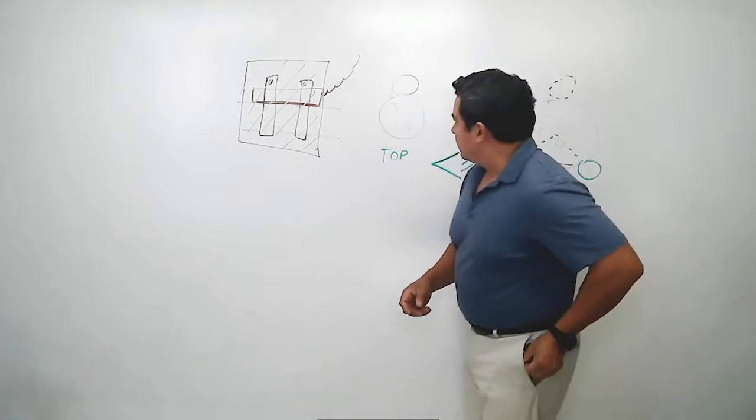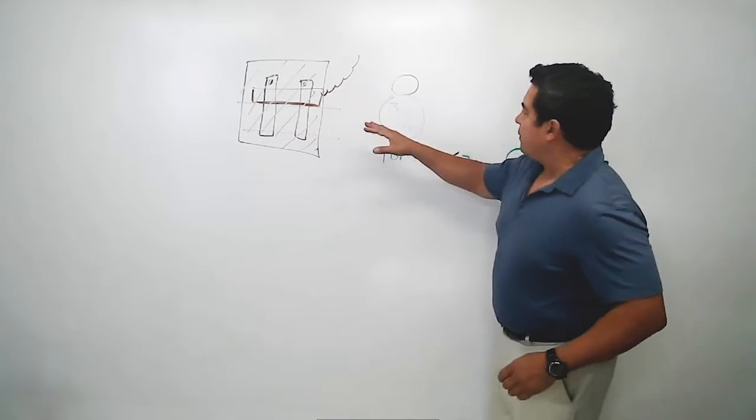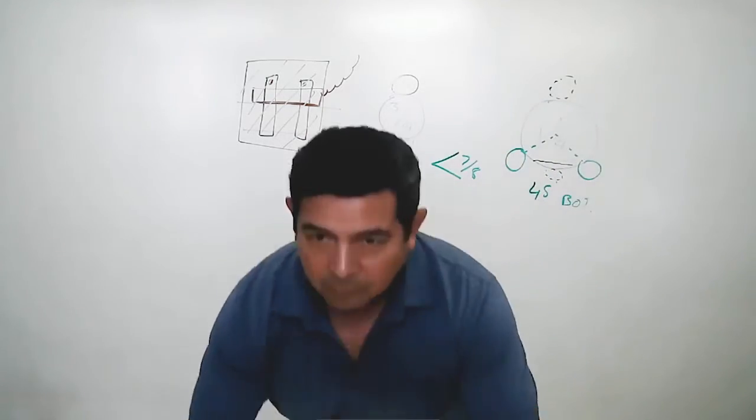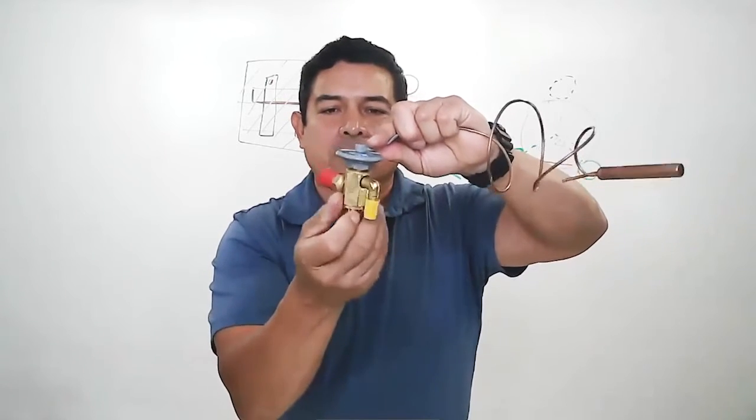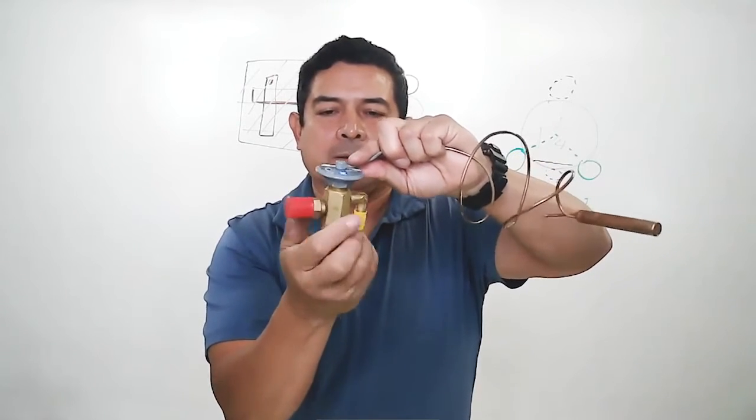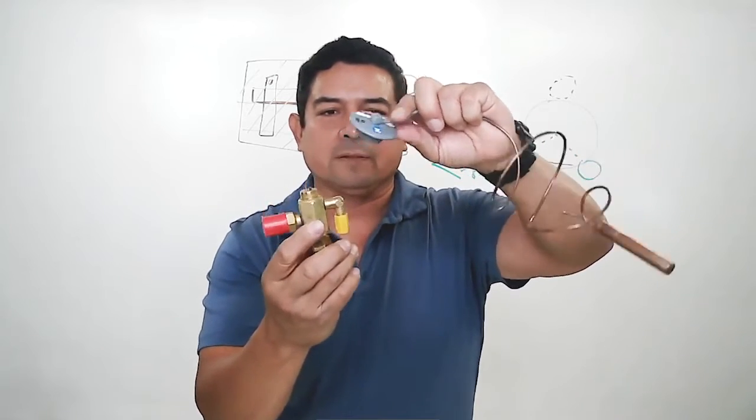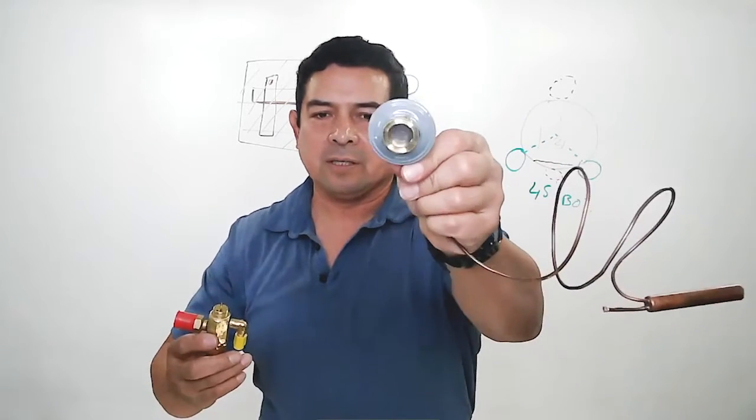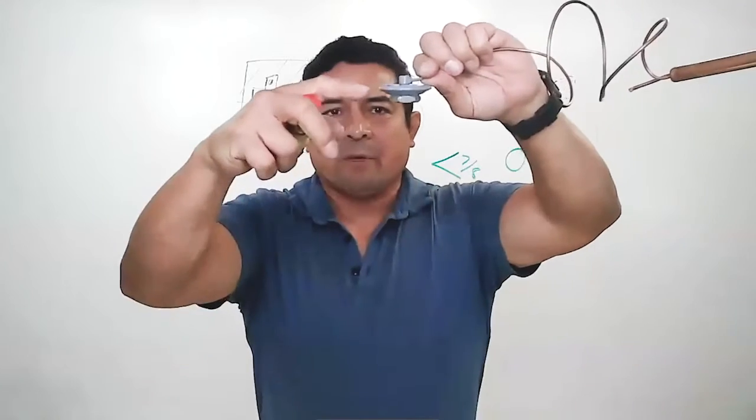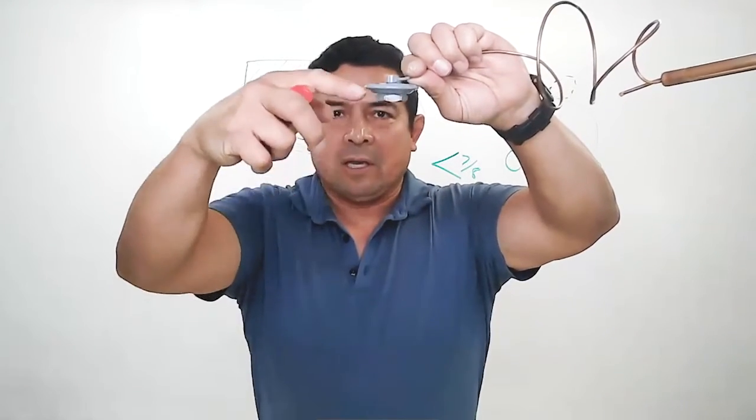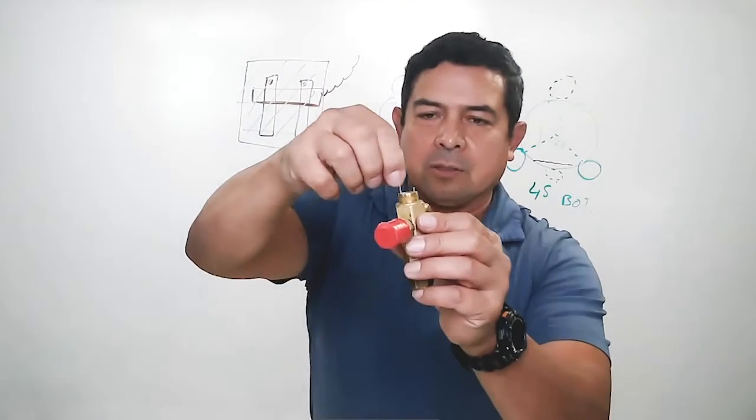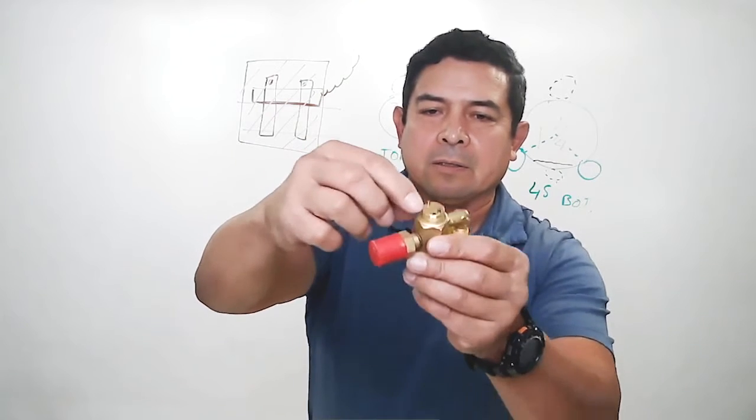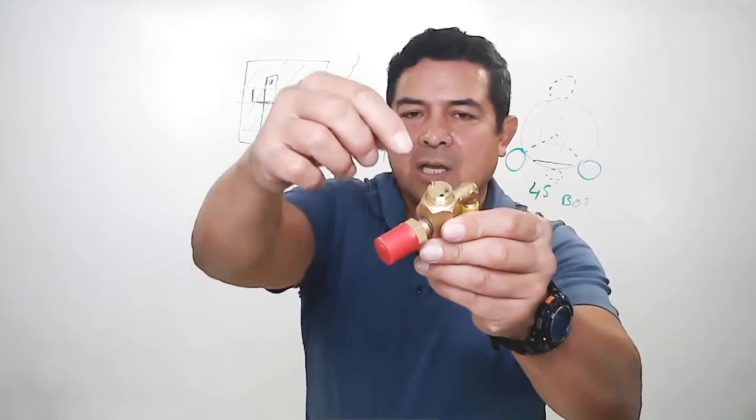So now we have the sensing bulb that we talked about, the power head right here. So this power head, it can come off. Once we take this off inside, we can see the diaphragm that's in there. When this senses temperature, the diaphragm is going to expand down and push down. Once it pushes down, it's going to take these pins that are here and push them down.